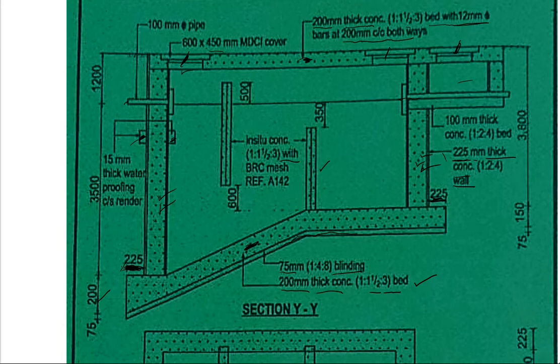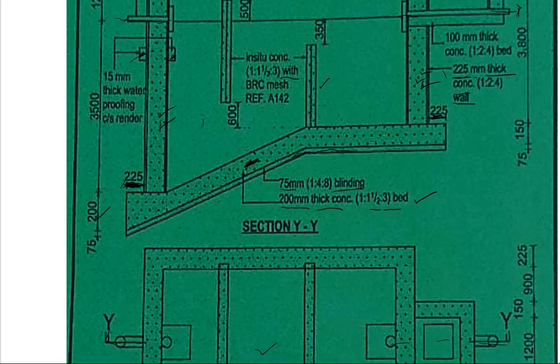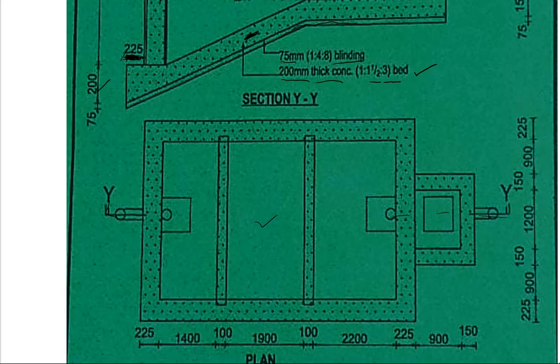We plaster our walls both on the outside and on the inside. The waste comes in, goes down — when it gets full it will pass up and exit through the manhole to the outside. Looking at the plan, the manhole dimensions are 900 by 900 millimeters, with an external dimension of 150 plus 100, and this leads to the outlet pipe.